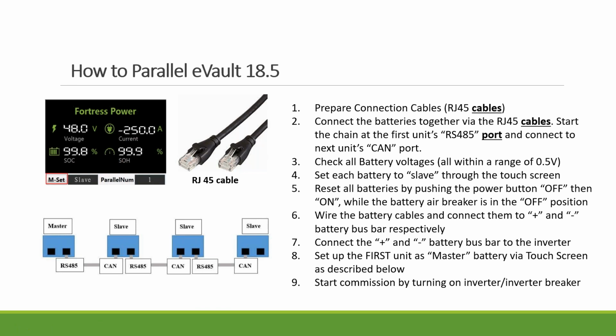With the eVault, there are a little bit more steps. Like I mentioned, it comes with the RJ45 cables, and then you can daisy chain them, so they will communicate with each other. You always start with RS485 to CAN, RS485 to CAN. And also, when it's connected, if the voltage between the batteries is greater than 0.5 volts, then the one with the lower voltage will not be turned on. Again, this prevents a problem: if you put two batteries in parallel and the voltage difference is too big, then the one with the higher voltage can charge the one with the lower voltage and send very high power. It could be a couple hundred amps and you could damage the battery.